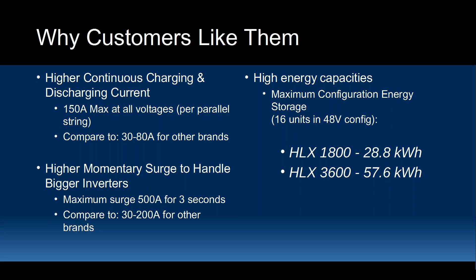And then the last note I want to touch on with these batteries is that oftentimes when we talk about lithium, there's a barrier, which is the allowable temperature range of these batteries. With lithium iron phosphate cells, you really don't want to ever charge the batteries below freezing. You run the risk of causing irreparable harm. Typically, they can be discharged at slightly lower temperatures, but for cooler environments, they really should be in an insulating enclosure, and you should ensure that the batteries are never charged below freezing.